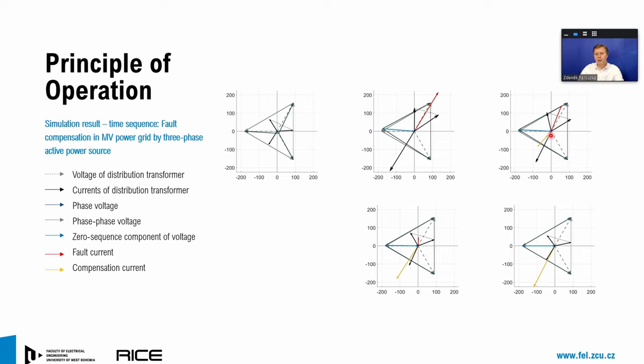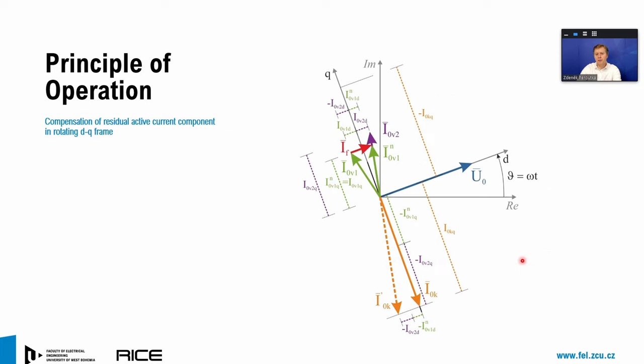And our current source starts immediately to compensate the fault current, producing the compensation current having the same magnitude and opposite phase. You can see how the compensation current rises and acts against the red fault current. And finally, we are able by our current source to fully compensate the fault current in the system. So that's the idea of how the system works, and this is the simulation result.